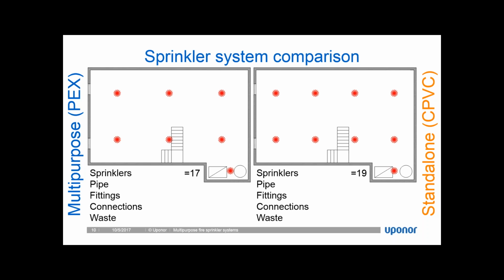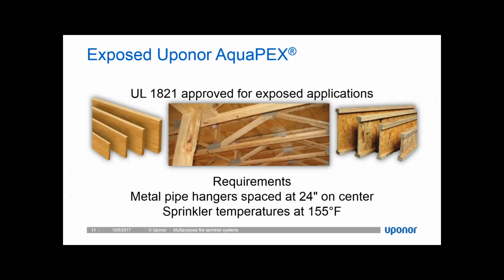And this all comes down to what we call exposed listing. So this basement is unfinished, and we want to install the piping in an unfinished application. Well, in order to do that, you need to have a listing that says you can install it exposed. And most piping manufacturers will have a specific listing for exposed. CPVC manufacturers have exposed listings, and Uponor Aquapex tubing has an exposed listing as well. Let's take a look at Uponor's and why we can use fewer sprinklers with an Uponor system.